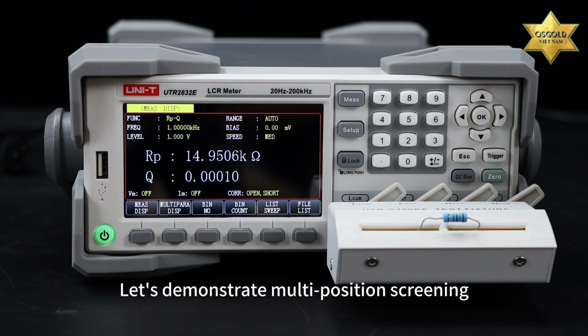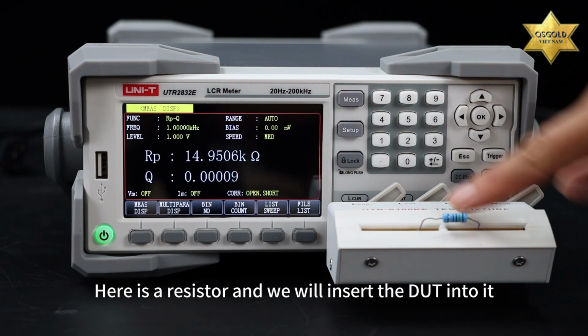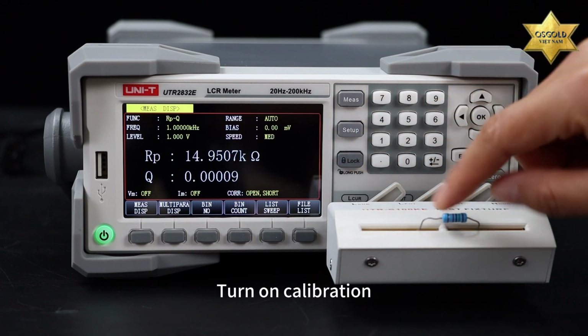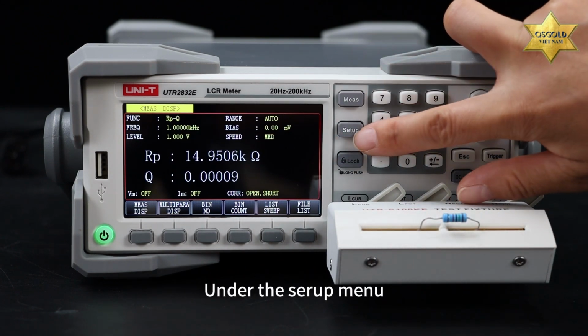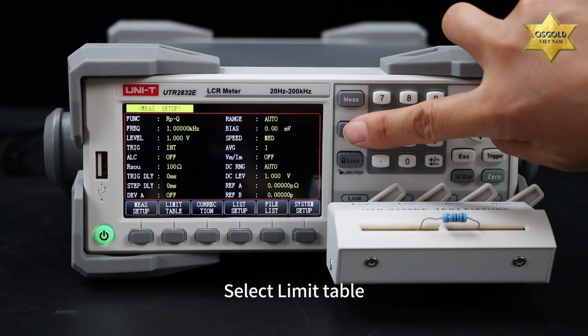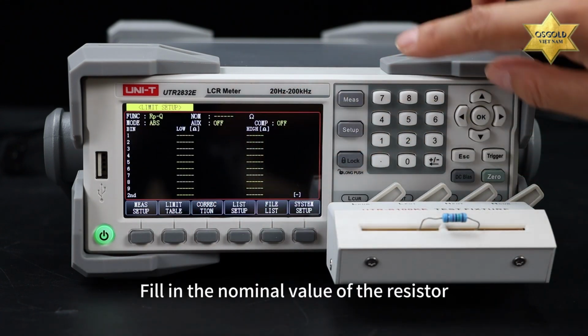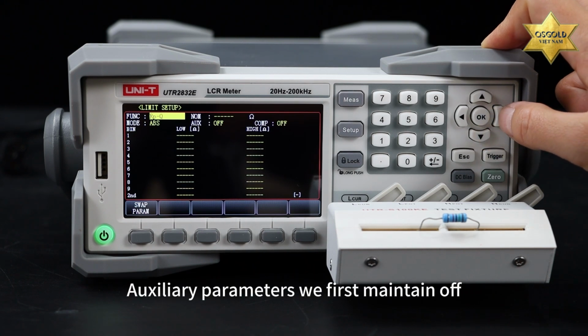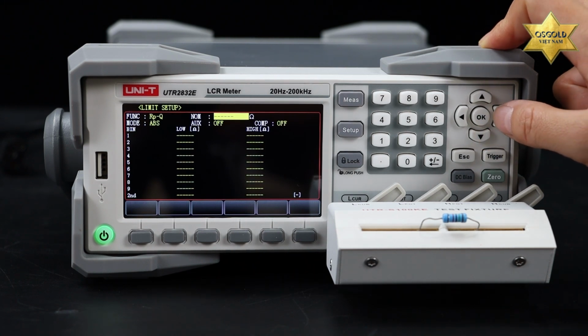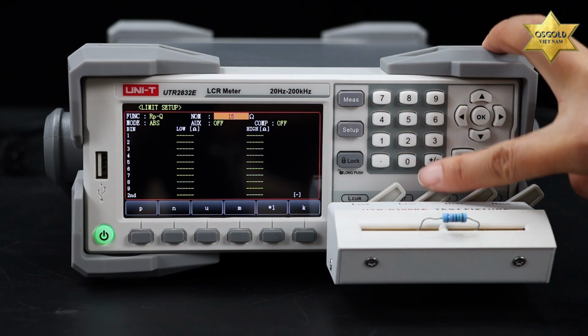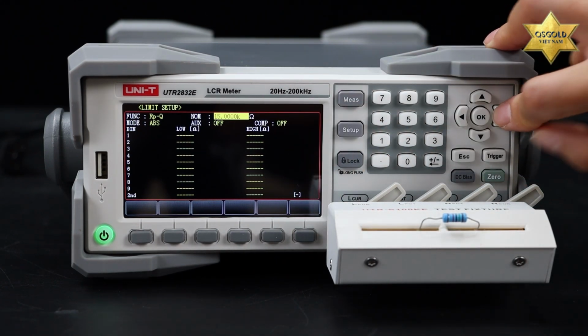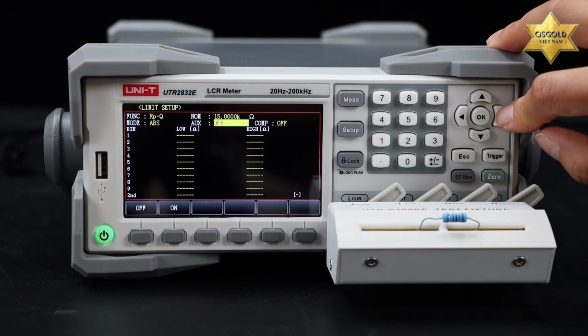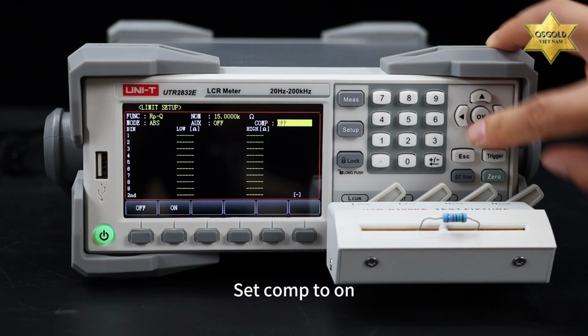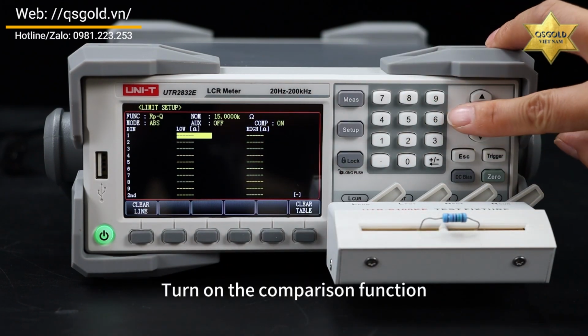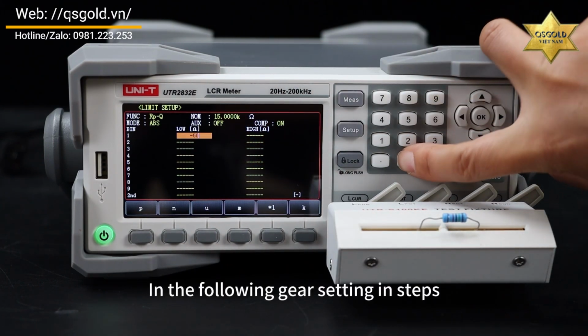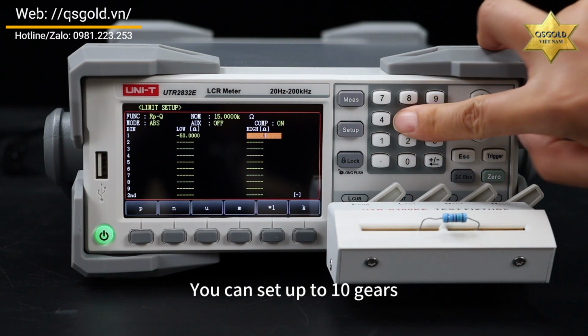Let's demonstrate multi-position screening. Here is a resistor, and we will insert the DUT into it. Turn on calibration. Under the Setup menu, select Limit Table. Set the corresponding parameter. Fill in the nominal value of the resistor. Auxiliary parameters we first maintain off. Set comp to on. Turn on the comparison function. In the following gear, setting and steps, you can set up to 10 gears.